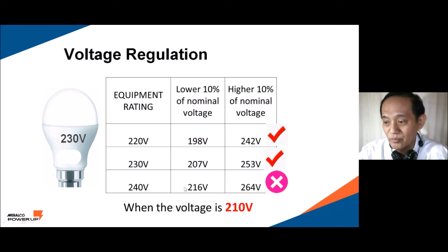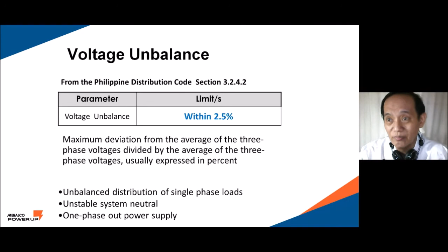So going to voltage unbalance, the maximum voltage unbalance by the PDC is 2.5%. And one of the causes that happened in SM way back 5-7 years ago is when the neutral of the SM tenant was not bonded to the ground of the supply transformer. So the 230 volts is not very stable and it caused an unbalance in the single phase 230 volts, which made them unable to operate their equipment. So when you properly bond the neutral and the ground, you have a stable 230 volts across all three phases.